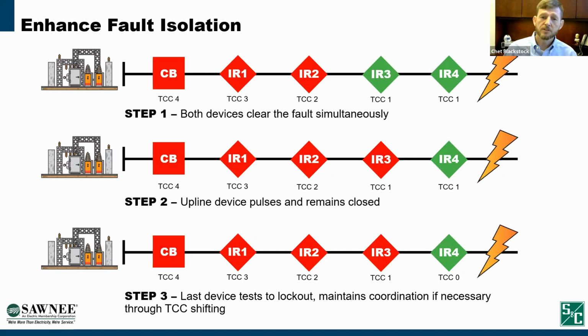So this is an example of how our system works now using the enhanced fault isolation. So in this example, interrupters 3 and 4 have the same TCCs. So both trip simultaneously initially. Interrupter 3 pulses, doesn't detect the fault, stays closed. And then interrupter 4 pulses all the way to lockout, assuming it detects the fault. If it doesn't detect a fault, then it shifts to the instantaneous curve. If the fault re-erupts within that 2-second hold time, it trips instantaneously, maintains coordination with interrupter 3 all the way to lockout.